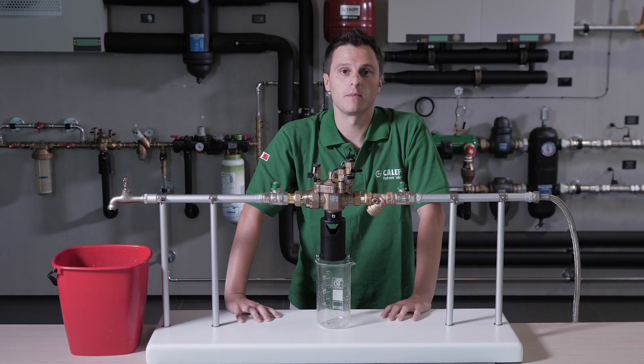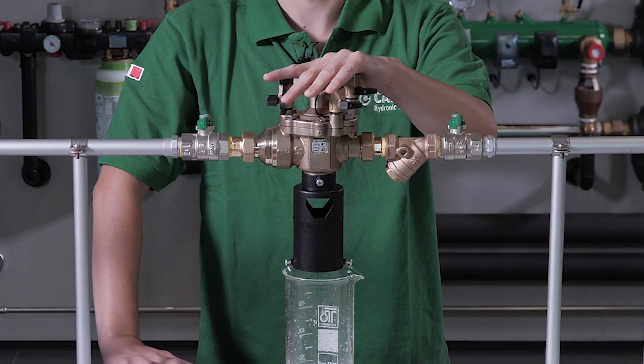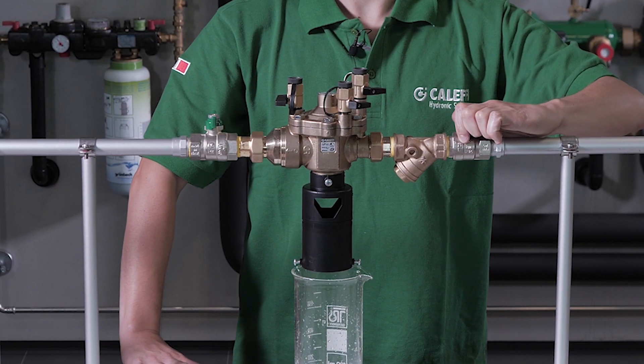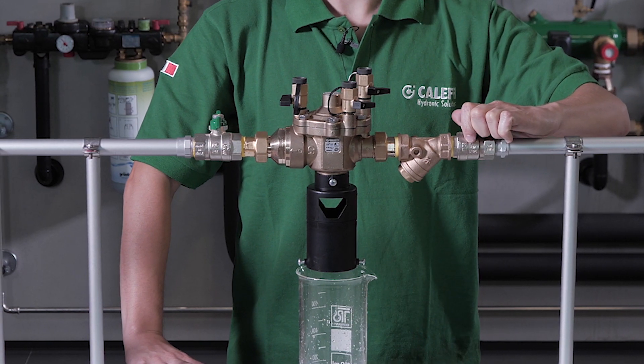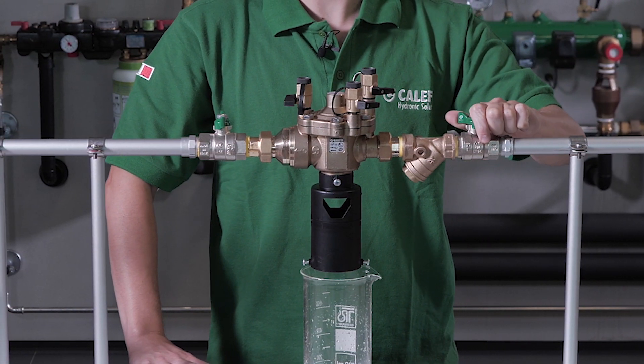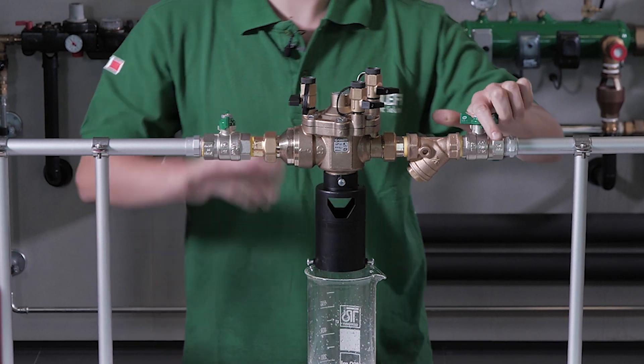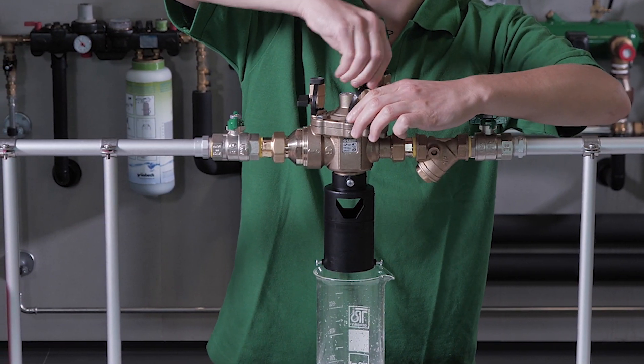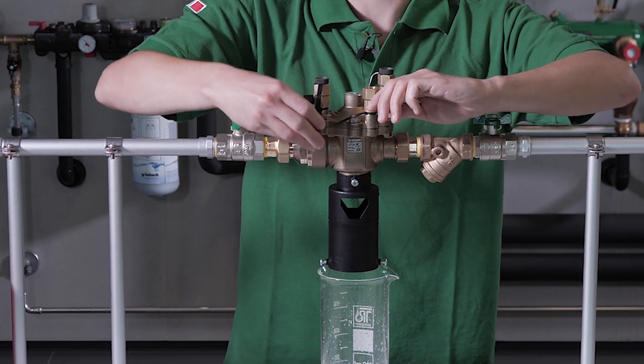After installation, the next step is filling the unit. To do this, slowly open the upstream shutoff valve and vent the air out of the unit by opening the pressure taps.